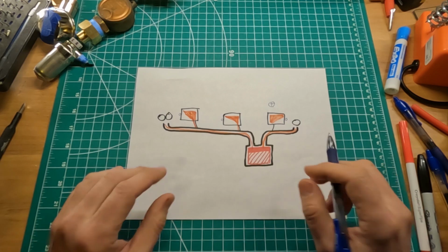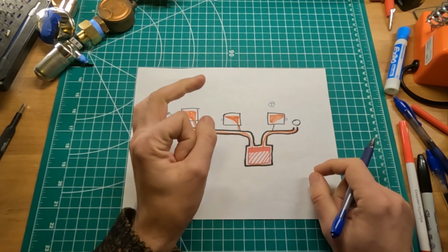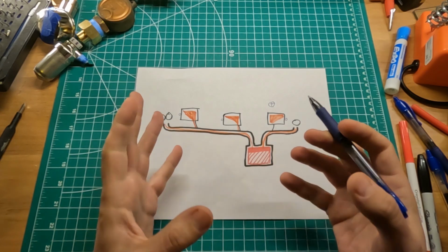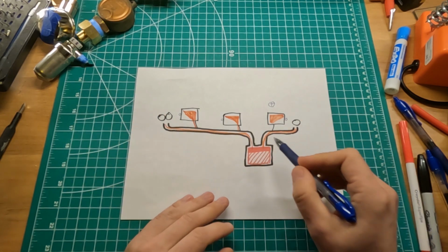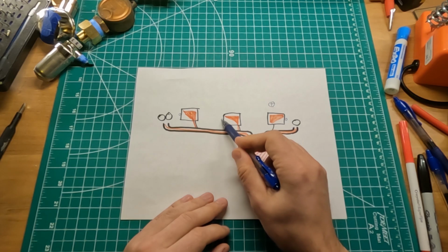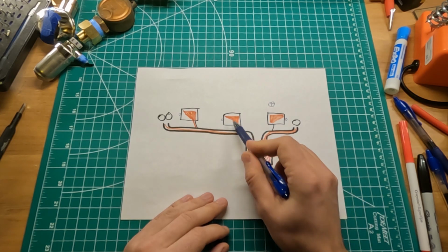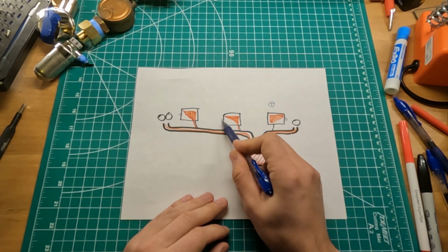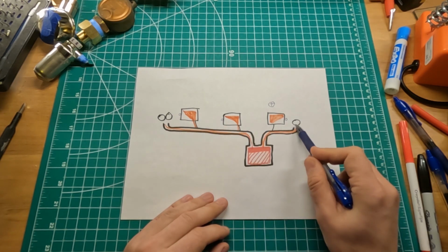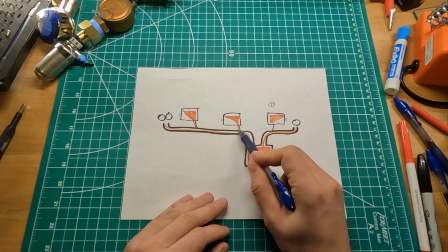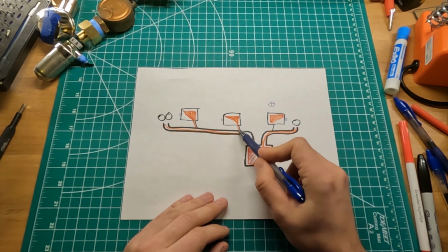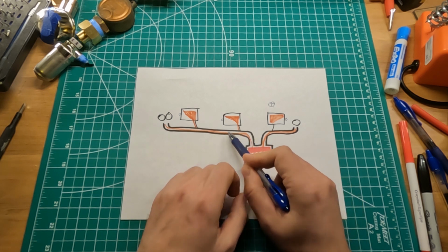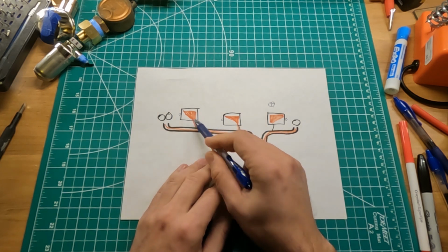system. Vents on the radiators by definition are much smaller, so because of that, the steam will, as always, want to go to the place of least resistance. So when the tiny little opening is here, the steam keeps on going, and might want to go to some other place, like let's say this one, instead of trying to be released by this opening, it wants to go to this opening right here. However, because there's already plenty of steam in the main, what ends up happening is just the little bit of steam that still travels this direction will keep on going to the radiators.